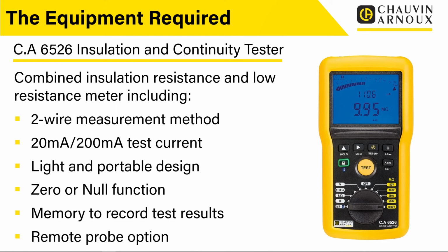So for those of you who are in the market for a simple backup to your multifunction tester, or something quick and easy to use if you just want to do some basic low resistance measurement or some insulation resistance tests, have a look at these, because they are a cracking little range of insulation continuity multimeters. We've included that because this is really the starting point in the range. But as we said, these are low resistance ohm meters, but we're not into the true 4-wire measurement.